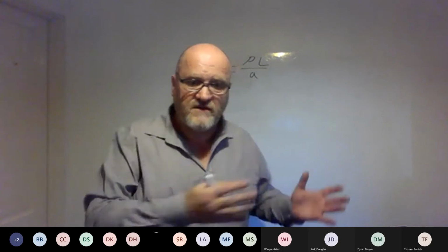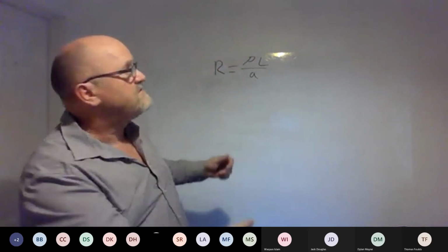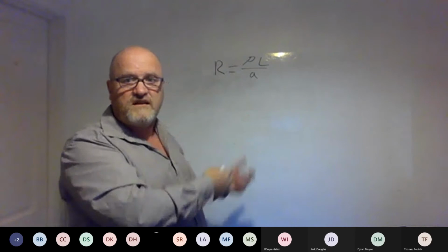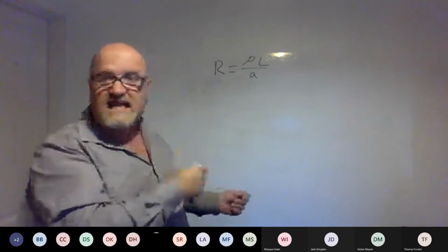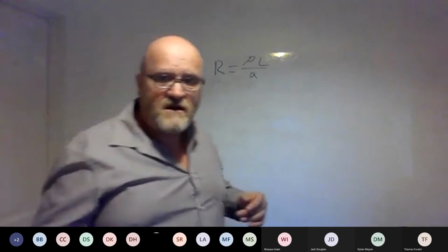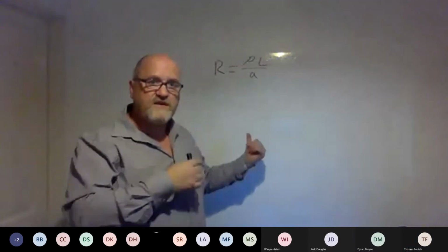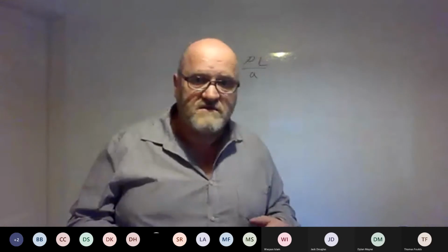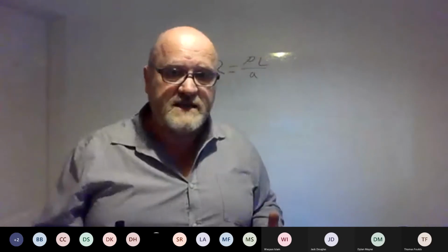And then you're just checking, when I've built it, that I'm testing it. I've got my lighting circuit, I've tested that, or I've got my ring final, I've tested that, and the readings are what I expect them to be. What's that tell me about my job in a couple of different ways? If I get all the readings I've worked out when I test it, what's that tell me about the actual circuits themselves? They're all good. Yeah. And if I've got these readings and they comply with what's in the regs, I'm complying with regulations as well. I'm ticking boxes without even realising it.